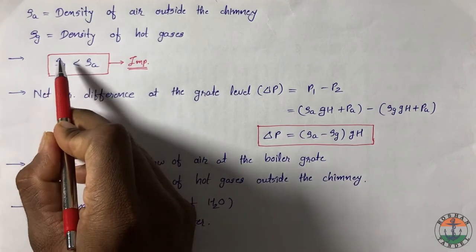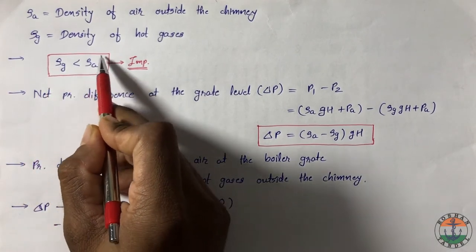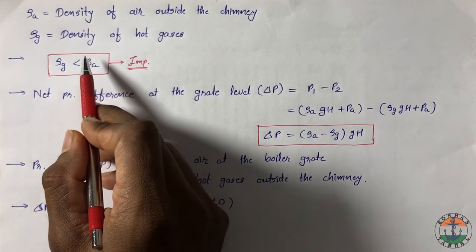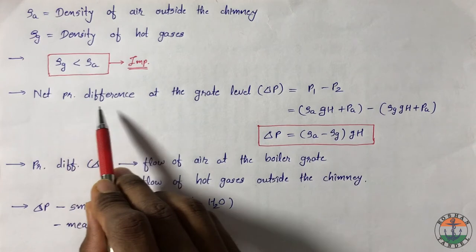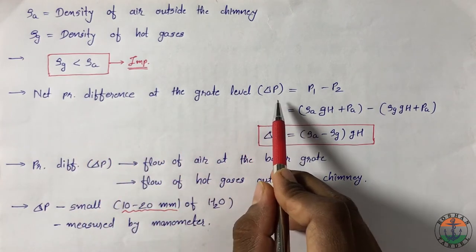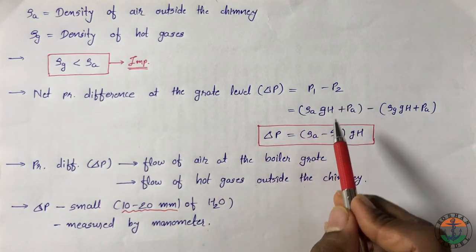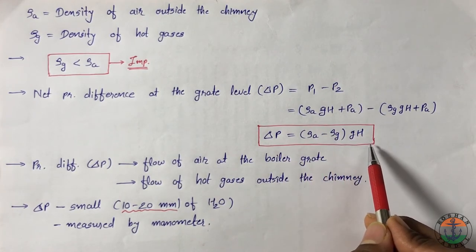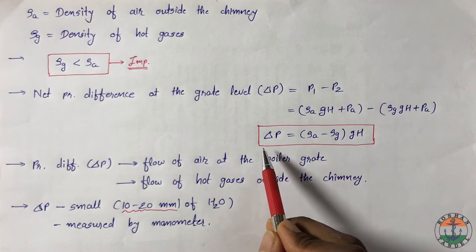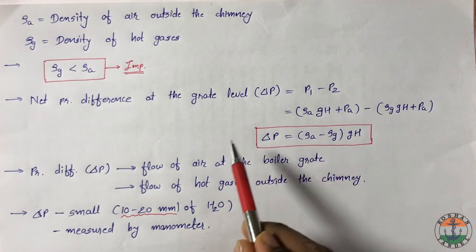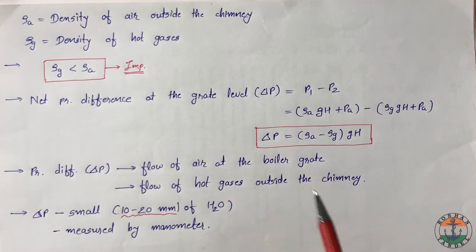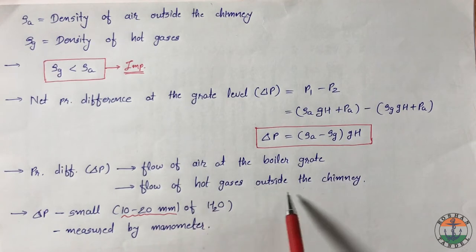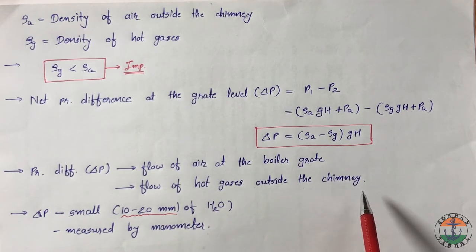Density of hot gases is less than the density of cold air outside the chimney. So net pressure difference at the grate level, delta P, is equal to P1 minus P2, giving us (rho_A minus rho_G) into G·H. This pressure difference causes the flow of cold air at the boiler grate and flow of hot gases out of the chimney, which is called draft.